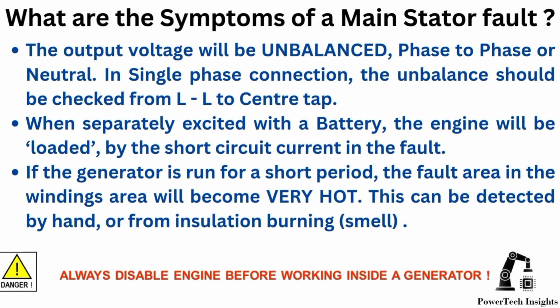Possible symptoms of a main stator fault. The output voltage will be unbalanced, phase to phase, or to neutral. In single-phase connection, the unbalance should be checked from line to center tap. When separately excited with a battery, the engine will be loaded by the short circuit current in the fault. If the generator is run for a short period, the fault area in the windings will become very hot. This can be detected by hand or from an insulation burning smell.